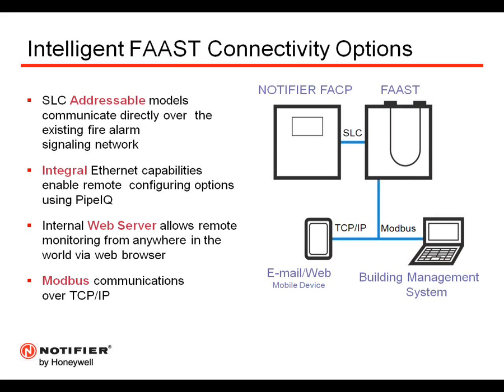FAAST also offers many connectivity options. The first is the SLC addressability, which Dan will go over in more detail. Second, FAAST has an onboard Ethernet connection, which enables remote configuration and monitoring when the device is set up with an IP network. This can be done using our PipeIQ software, or FAAST also has an internal web server, which allows the device to be viewed from anywhere in the world as long as you can connect to that local area network that the FAAST is sitting on.